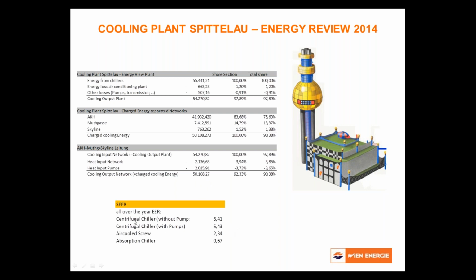So when you talk about energy efficiency, what is the comparison? We have also there in Spittelau an air-cooled screw, which is almost a system a customer would install by themselves. They won't make a recooling via river water - that makes no economical sense. So the efficiency of the machine would be around 2 or 2.3, which is quite low. But our chillers make 6.4, depending if you calculate the pumps, 5.4. So we have almost doubled efficiency only in the electrical way, and there is no waste incineration included.